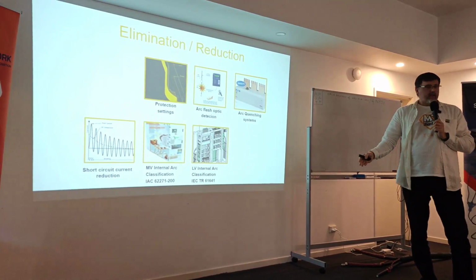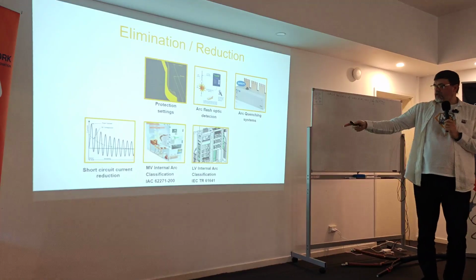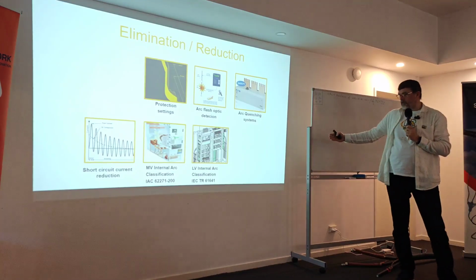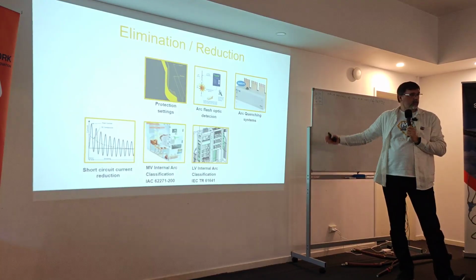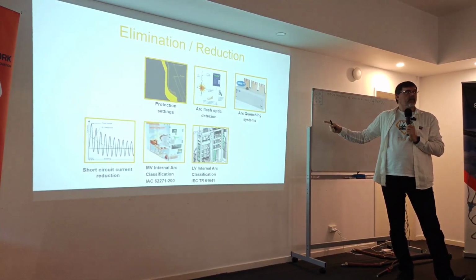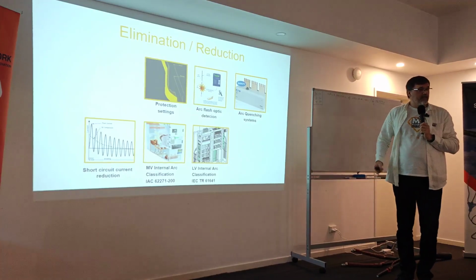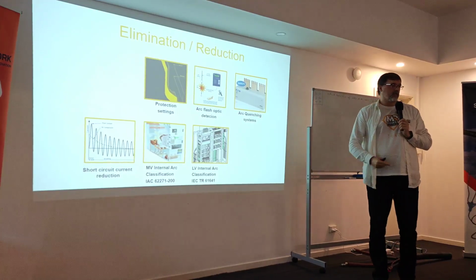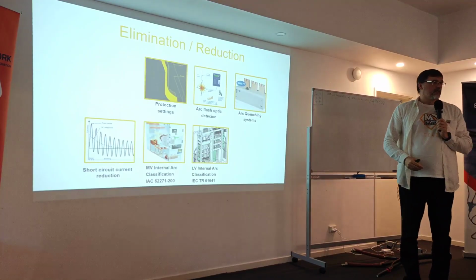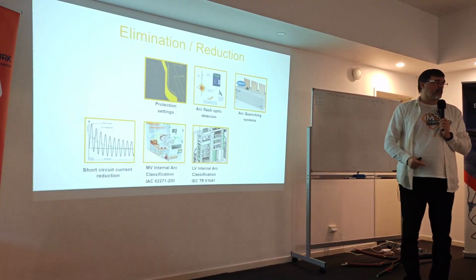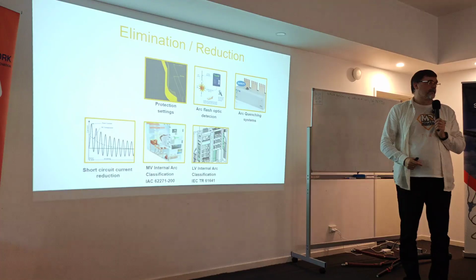There is a trick behind it, which I think I will not explain today, but there is a trick that you always do the test 30 centimeters away from the panel. There are some cotton testers. If they don't catch the fire, it's okay. If they catch fire, it's not okay. Which at the end means that if you stay 30 centimeters from the panel or closer, and you don't wear at least 100% cotton, you might catch fire. But the panel is arc rated.